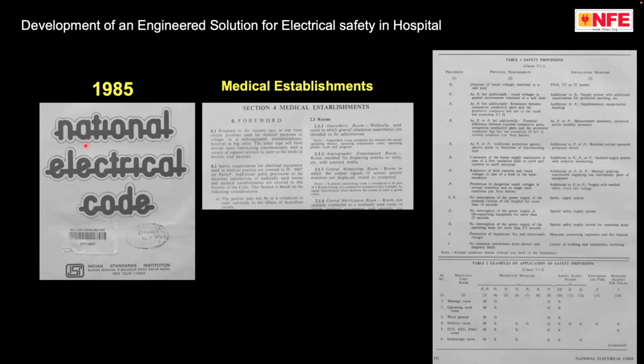For the first time in India, electrical safety in hospitals was introduced in 1985 in the National Electrical Code of India. As you can see here, Section 4, medical establishment. This standard talked about safety requirements in the entire hospital. Also, you can see on the right side, provisions, principal requirement, and installation measures. The safety measures are classified from P0 to P7 and some special additional measures, such as duration of touch voltage restricted to a safe limit. Like this, different methods were introduced in 1985.